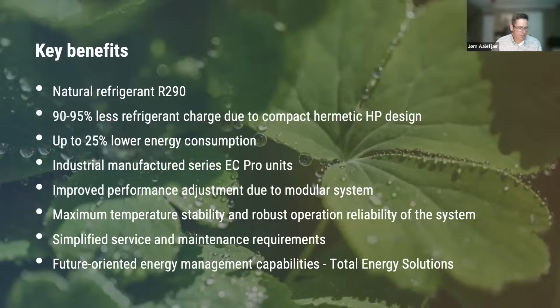Our heat pumps are industrially manufactured. It means it's not tailor-made. It's a serial-made heat pump, so we have the economy of scale advantage in this concept. I would also add that we can interface with more or less any other supplier's condensing units or CO2 hybrid systems or whatever you use. We have an interface system which allows us to talk to more or less any controller on the market right now.